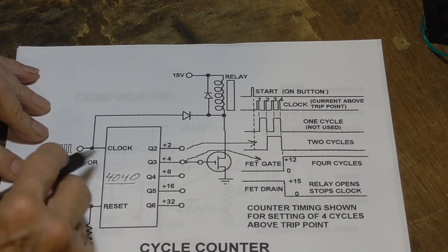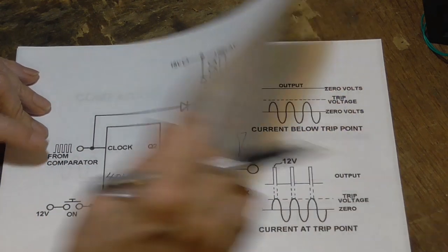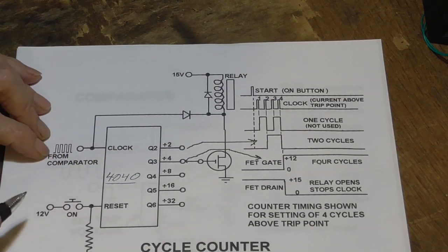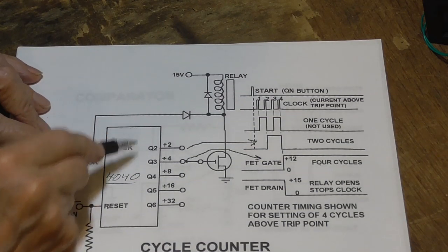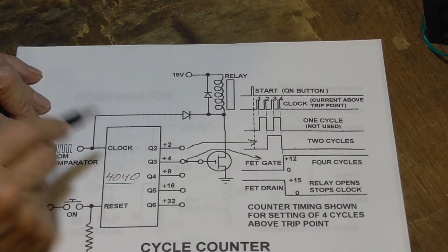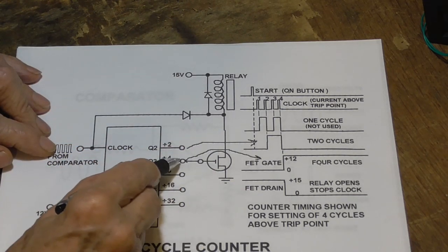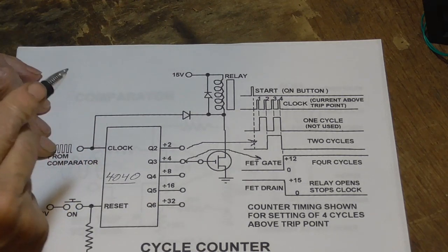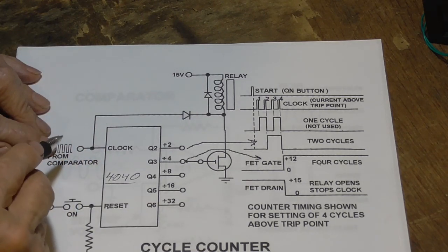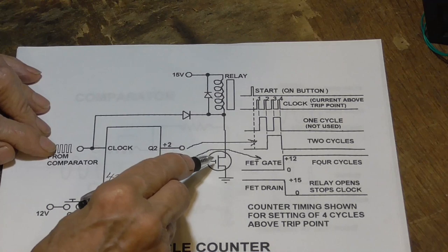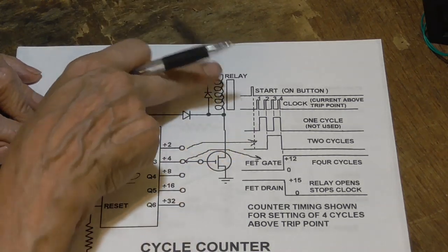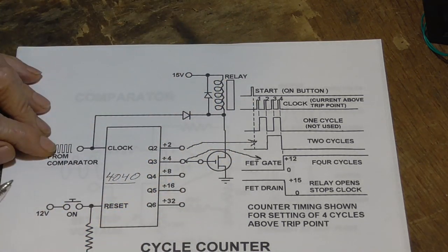Now, we take our output from our comparator, which is our pulses from here, and we put them to the clock. So each time we get a pulse, we step that counter one count. When we get two, if we have this set to 2, if we get 2 cycles that are above that threshold, it'll go ahead and activate the FET, and it'll pull in the relay, and that'll break the main power circuit.